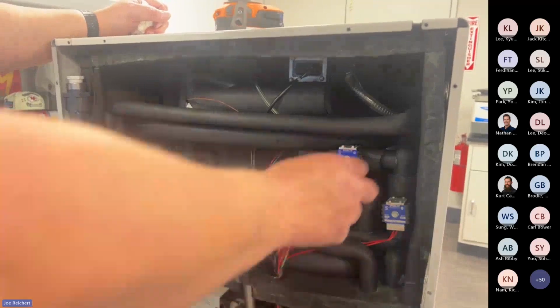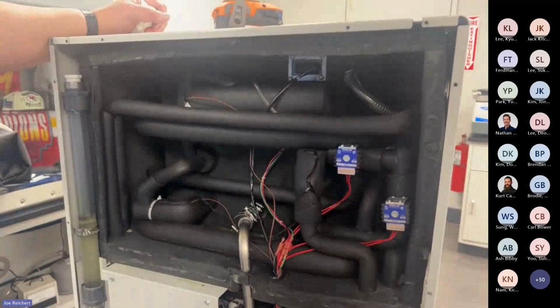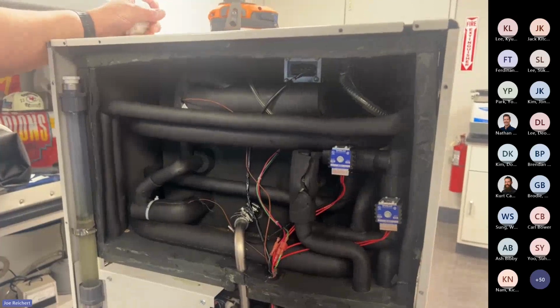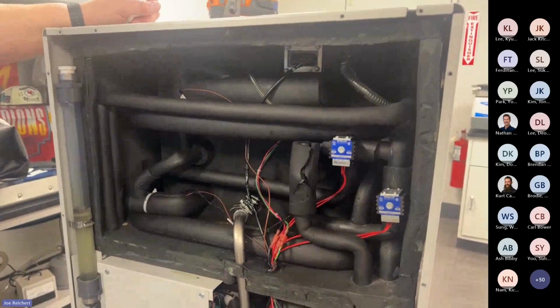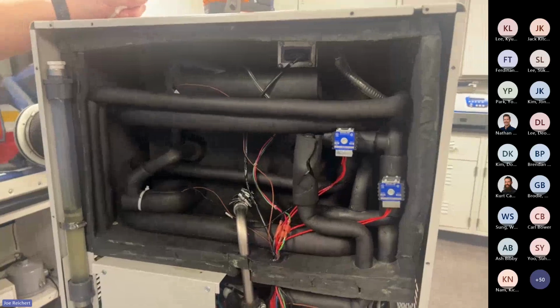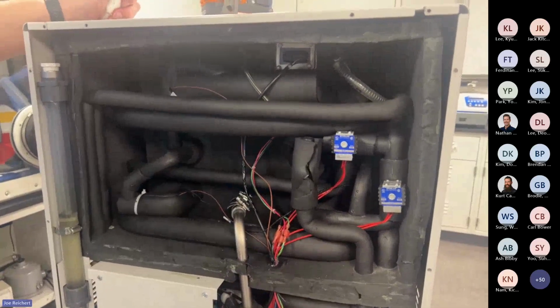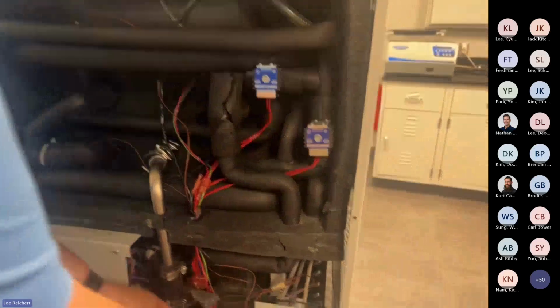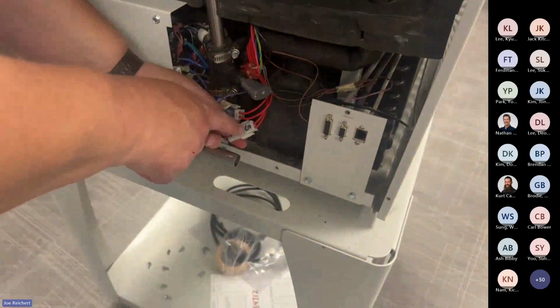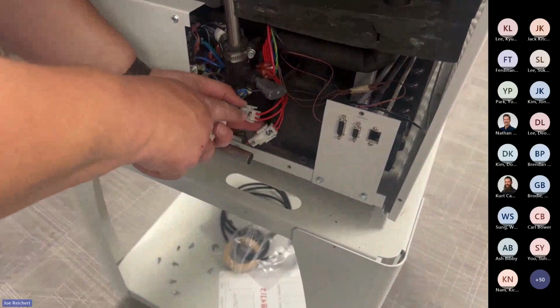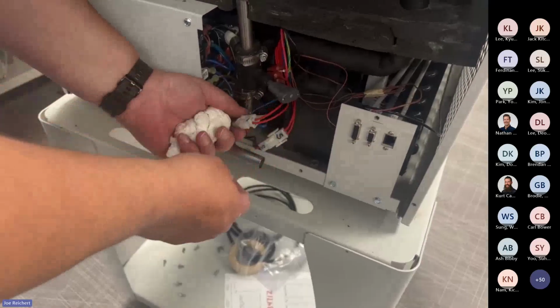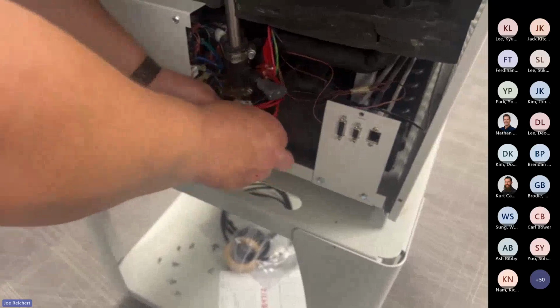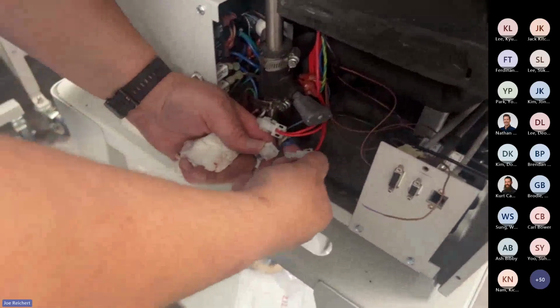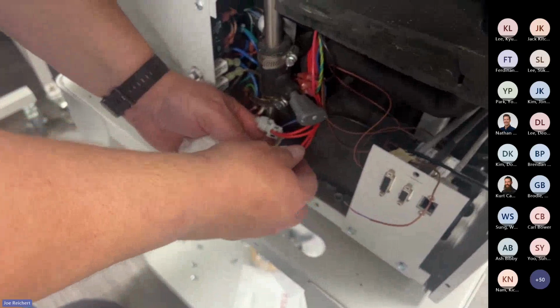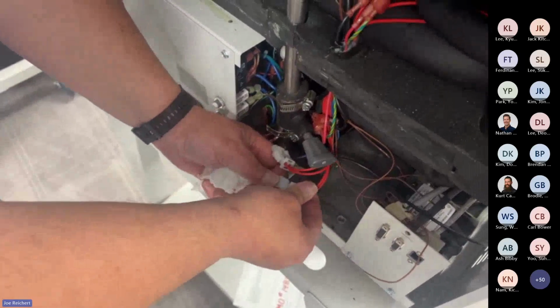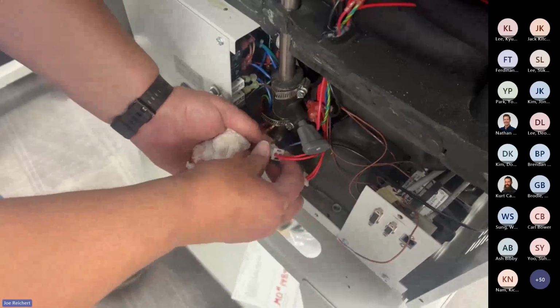In a few cases I've seen a valve stick that hurt the temperature on the shelf. You would get a partial temperature on your collector. The shelf was colder than it was supposed to be because it was sharing the gas between the two. But you can always check the valves very quickly. This one is for shelf, this one is for collector, and these are the valve wires. So when you're in max cold, you can take this connector and just disconnect it, and you can hear that valve clunk, close and open and close just by plugging it in and disconnecting it. You can hear that valve move.